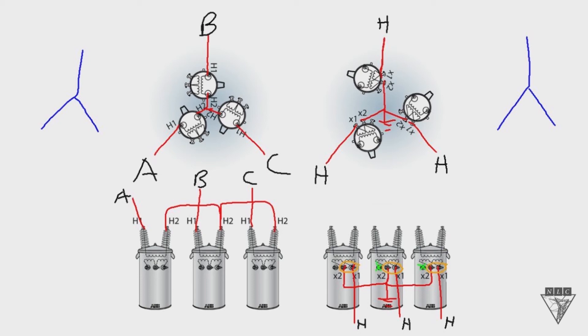Well, when you do that, when you're only utilizing two of the secondary bushings, you need to parallel the secondary coils together. If you don't parallel the secondary coils together, then you're not going to utilize the full KVA rating of the transformers.